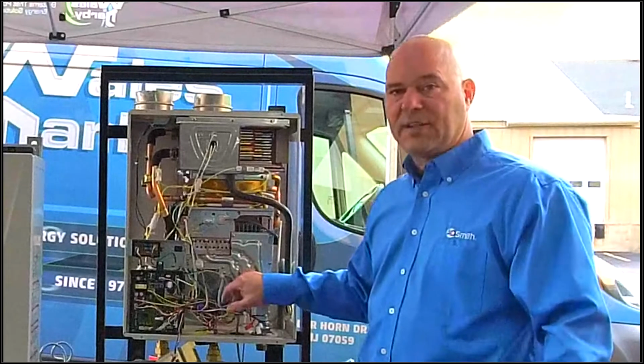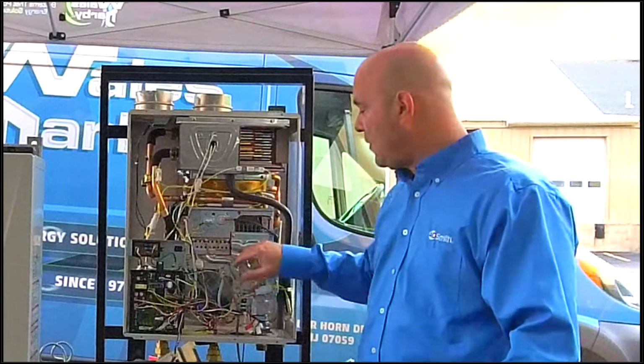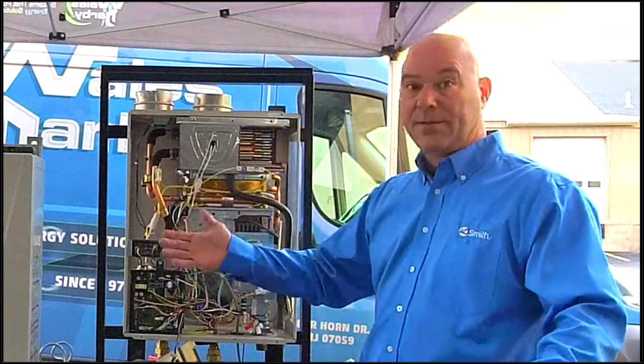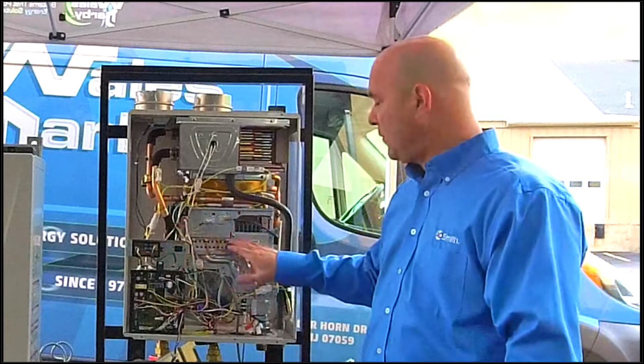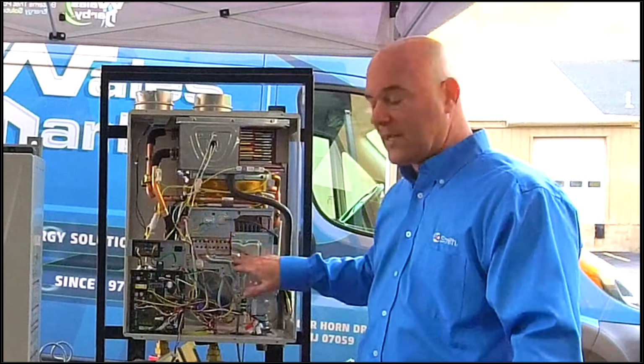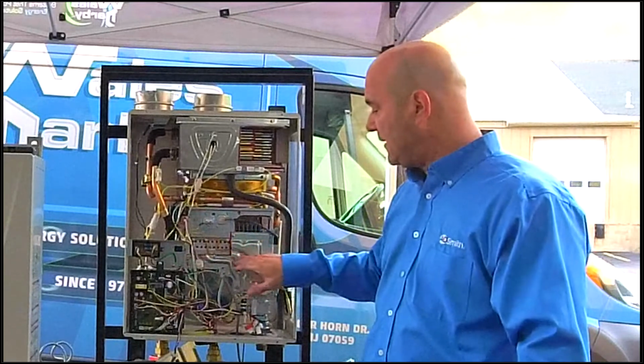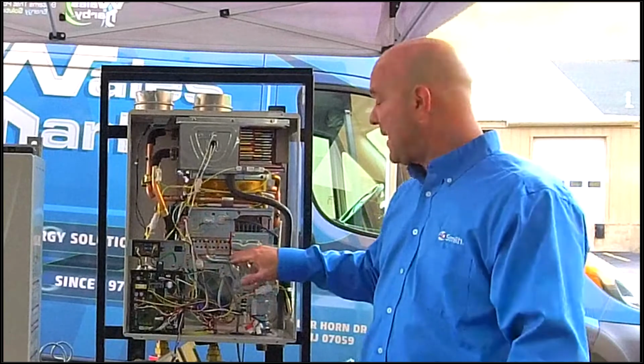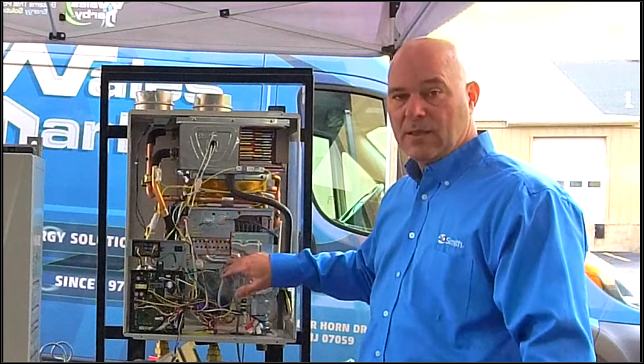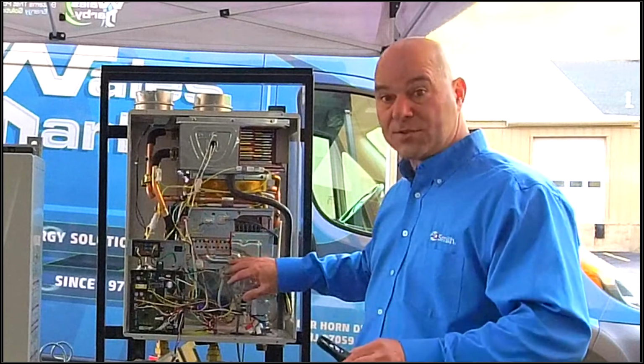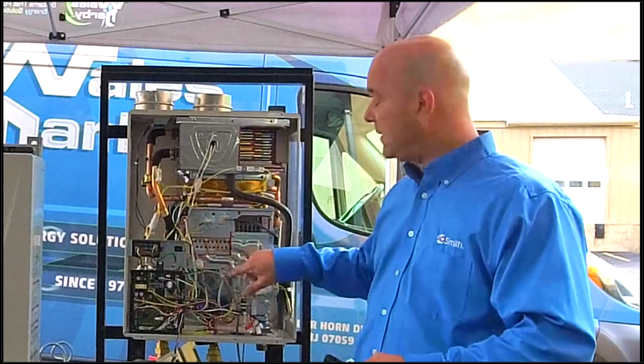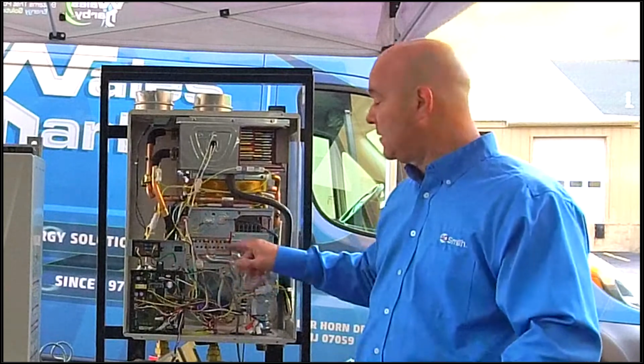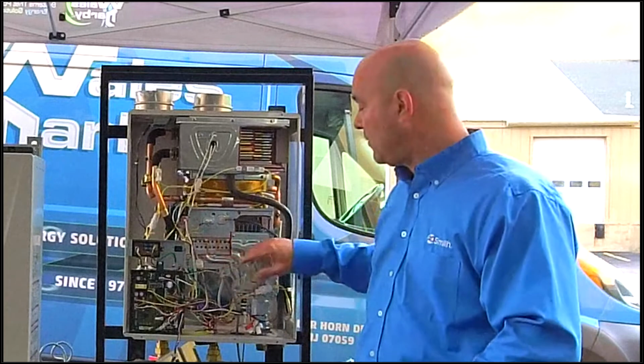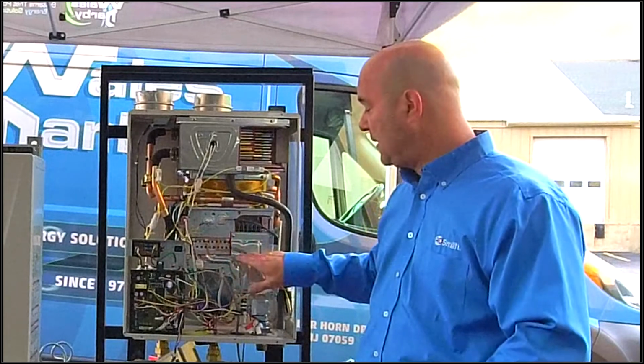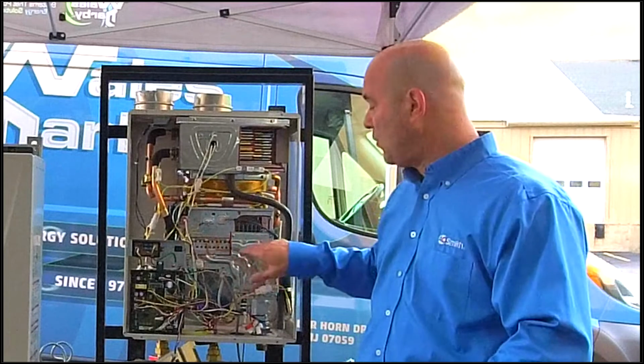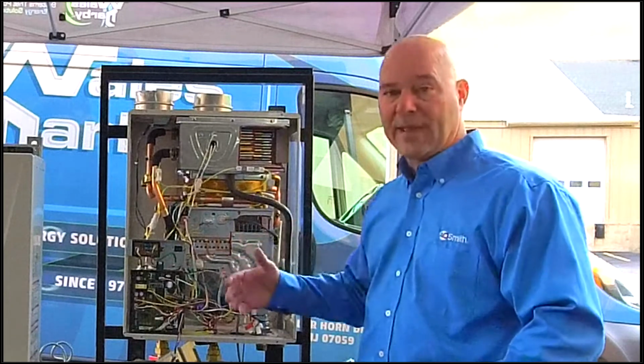We also never shut the gas off when there's a demand. So we could have all 3 tracks on, but really we need 1.5 gallons of hot water, so we'll step it down to marry up to whatever we need, one gas track. If this gas track is on and it's supporting the demand, and then there's another demand, it will pull on gas track 2. And if there's still a larger demand, it will pull on gas track 3, then it'll shut off 2. And then if it's a full demand, it'll pull 2 back on. So if it's a full demand, all 3 will be on. If it's a partial demand, it could be 1, it could be 1 and 2, it could be 1 and 3, depending on the demand.